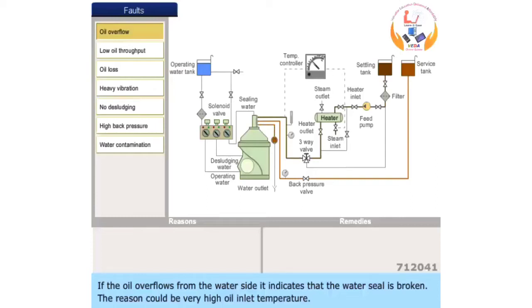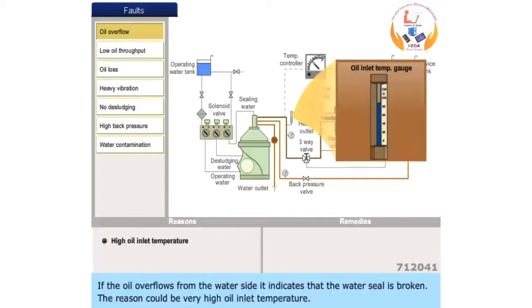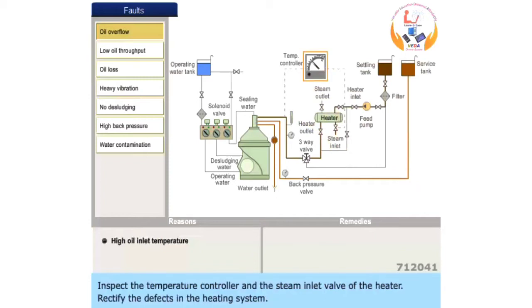If the oil overflows from the water side, it indicates that the water seal is broken. The reason could be very high oil inlet temperature. Inspect the temperature controller and the steam inlet valve of the heater. Rectify the defects in the heating system.